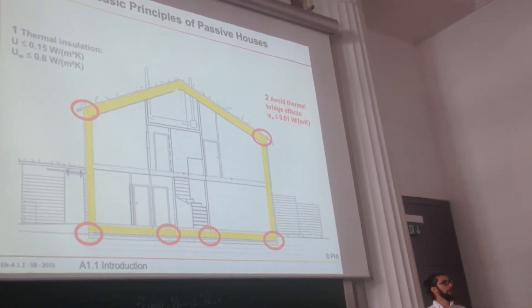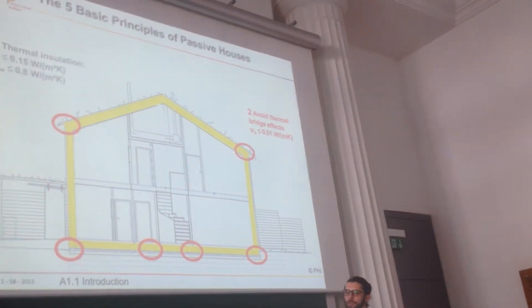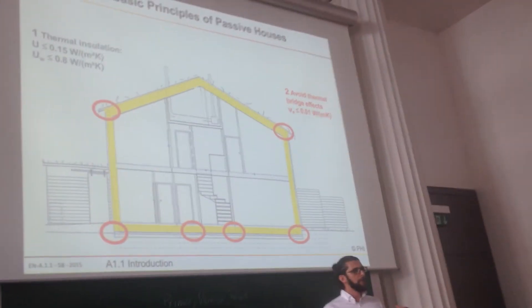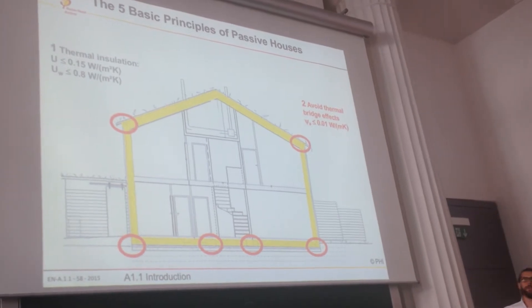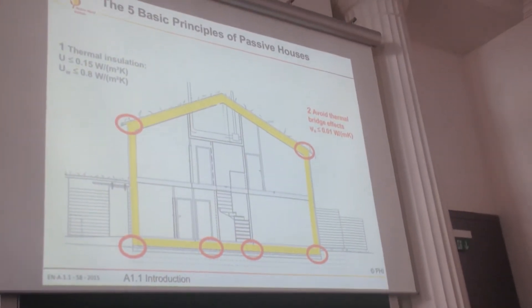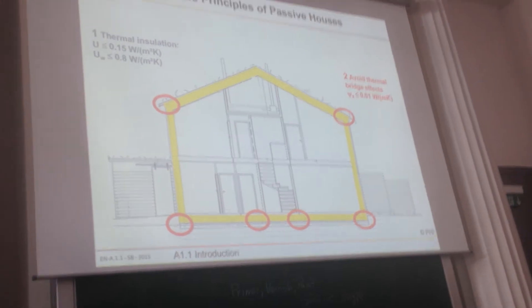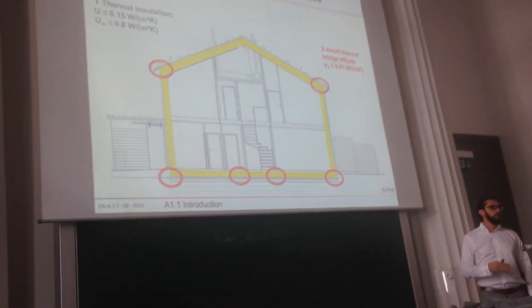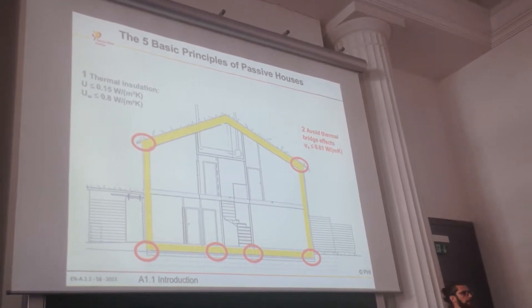Heat bridges — we can calculate heat bridges. I'll show some examples later on. But they are always the same. Every building has corners, every building has connections to the ground. You have to mark them and look at the details — is it possible to optimize this? Make a fast two-dimensional calculation, calculate the psi value. This is for heat bridges. And if it's below 0.01 W/mK, then it's fine.